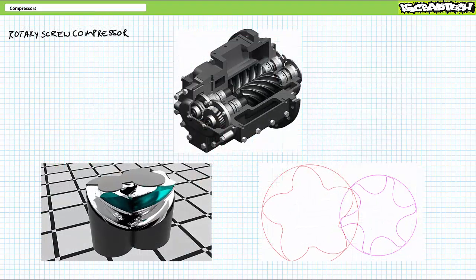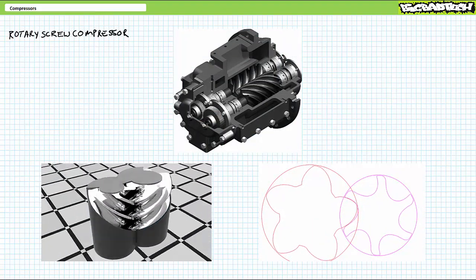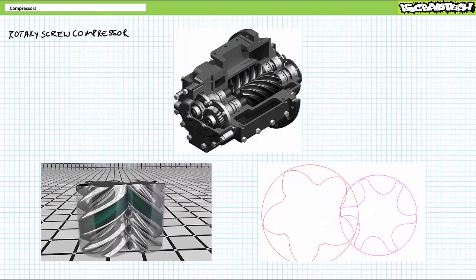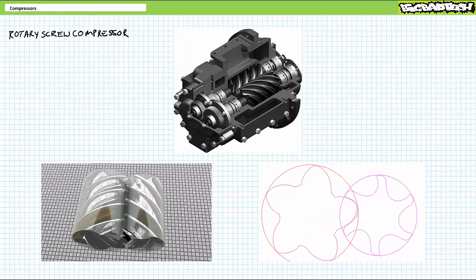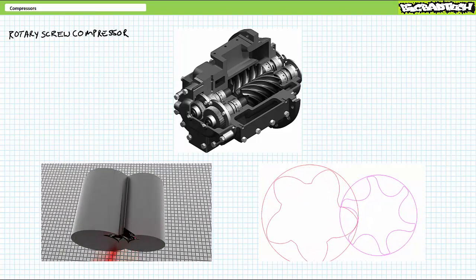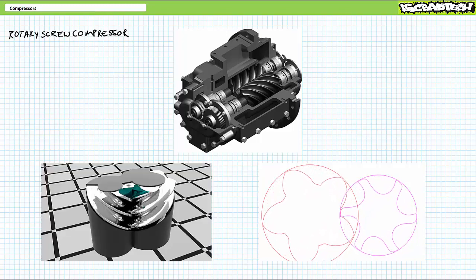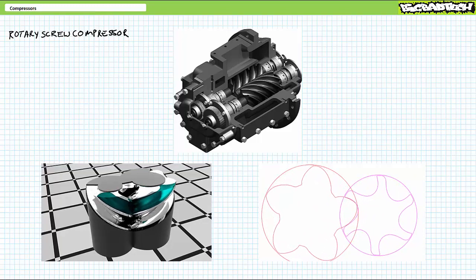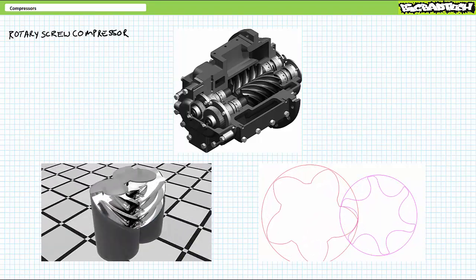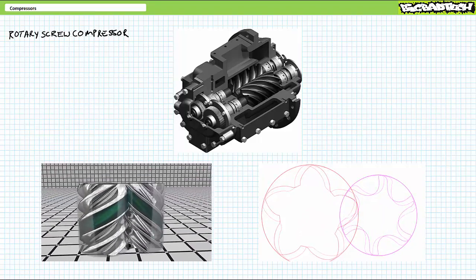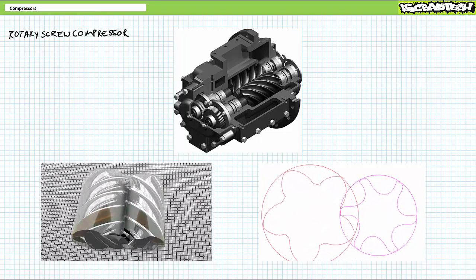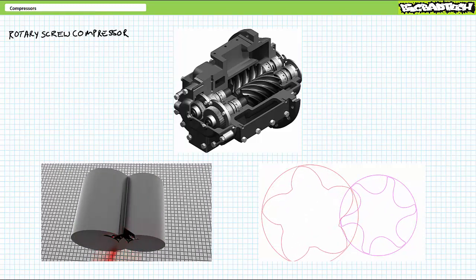The third type of common compressor is the rotary screw compressor, which is a little difficult to illustrate using simplistic diagrams, so rather than learning how to use computer graphics software, I just stole these publicly available images from Wikipedia. A rotary screw compressor consists of a closely mated male and female screw where the thread spirals the length like a coil of DNA. As the intermeshed spiral rotors turn, they form chambers within the thread in the casing walls enclosed by the circumferential edge of the spiral. As the individual chambers move from inlet to outlet, volume is reduced compressing the gas and expelling it into the pneumatic system.